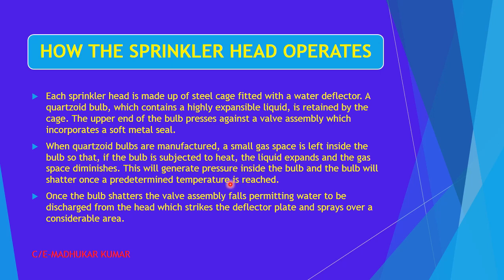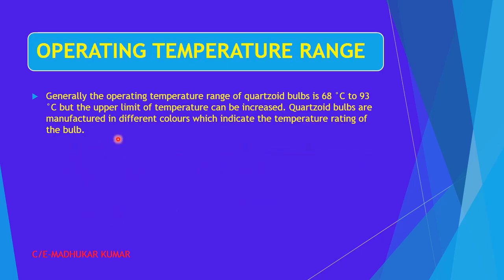I hope you have understood. It is already explained in the earlier slides also. Once the bulb shatters, the valve assembly falls, permitting water to be discharged from the head, which strikes the deflector plate and sprays over a considerable area, or you can say the coverage area as per the requirement. Regarding the operating range, generally the temperature range of the quartzoid bulbs is 68 to 93, but the upper limit of temperature can be increased also, as we have seen in the earlier part. Quartzoid bulbs are manufactured in different colors which indicate the temperature rating of the bulb, which we have seen in the earlier slide. As per the various temperature ranges, we have different colors of bulbs.